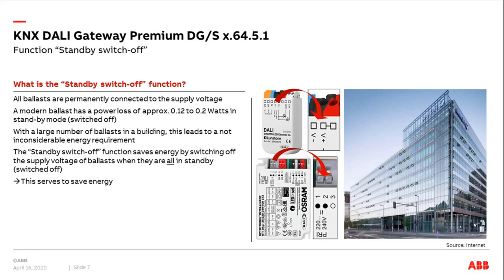Now, what does the standby switch-off function mean? All ballasts are permanently connected to the supply voltage — for example, a DALI driver for low voltage or a 230V DALI ballast always connected to mains. A typical ballast today has a power loss of between 0.1 and 0.2 watts when switched off, placing it in standby mode. Old ballasts may have more than one watt.